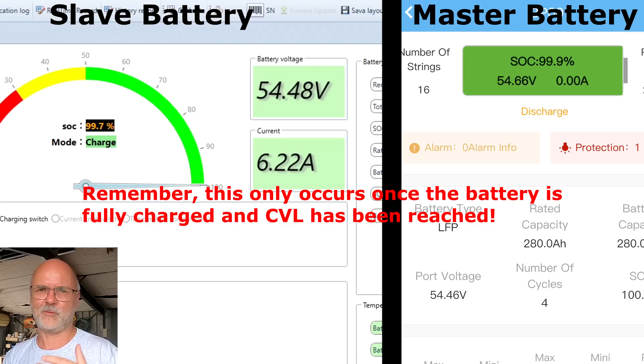Now slave and master battery have the same voltage, but we are charging only the slave battery. Charging is still disabled in the master, so the slave will hit 55.2 volts at some stage, while the master will stay at this point.